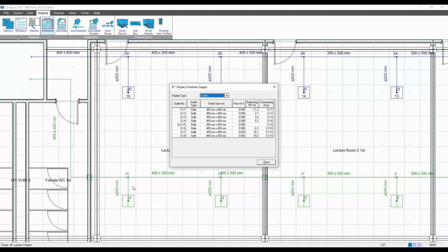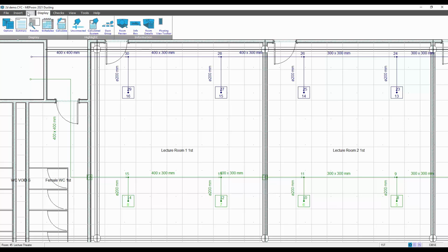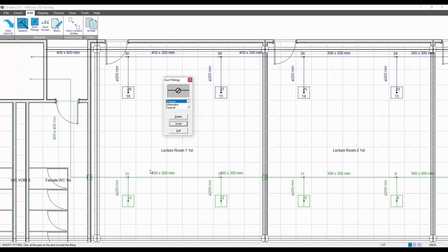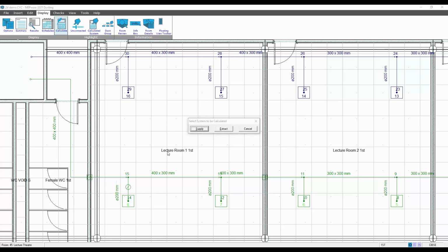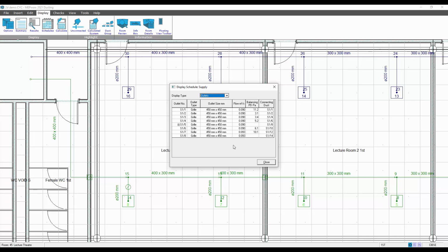When I put the balancing damper in on the branch, I put the resistance in relating to the balancing pressure in the tables of 19.3 pascals. Edit, duct fittings, select the damper, insert, select the duct, and then insert that residual pressure I'm balancing against of 19.3 pascals. We then rerun the calculation and update, then view the schedule. We can then see we've now absorbed the pressure at that branch. So we would repeat for each and every branch.